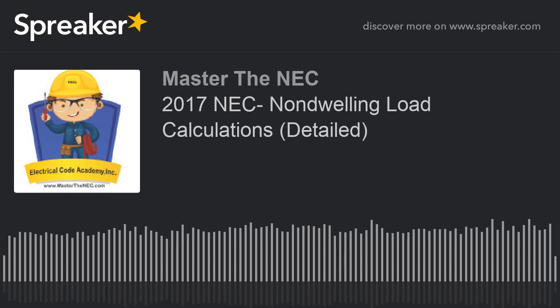So, again, if I've only got 2 things in here, maybe I only have commercial electric cooking equipment, 1 unit, and I have a dishwasher booster heater, and that's all I've got, well, that's only 2. I've got to take them at their full value. Now, when I start getting more than 2, and 3, 4, 5, and 6 and more, then I get to apply some additional demand factors to the loads that I'm talking about, okay? So, again, really got to know what equipment you're dealing with. And one thing to remember, table 220.56 does not apply to space heating, ventilating, and air conditioning equipment. It does not. We're talking about kitchen equipment.